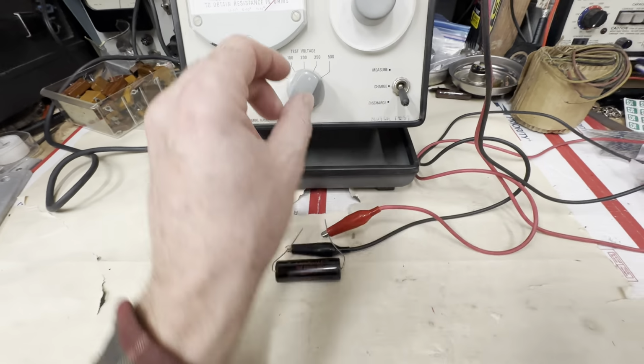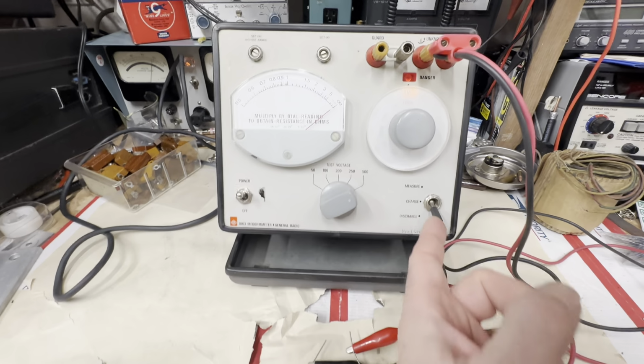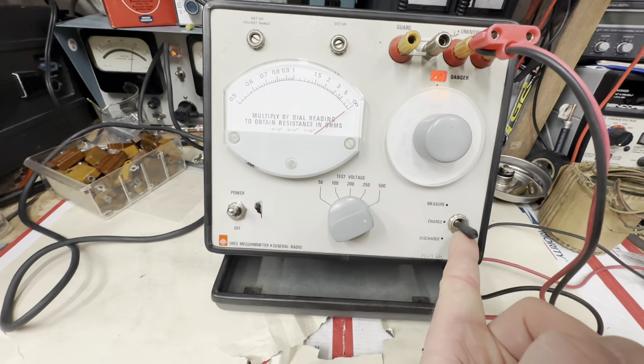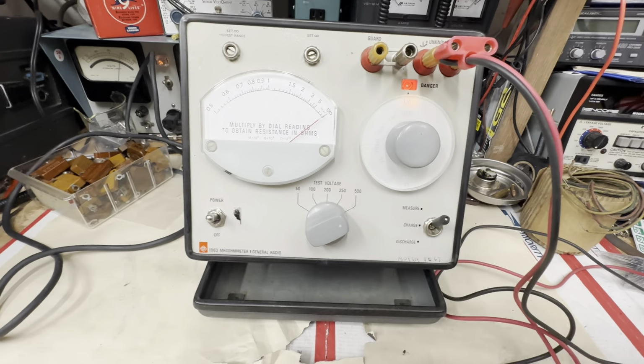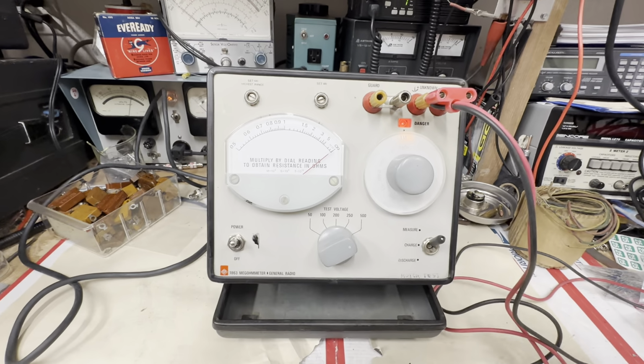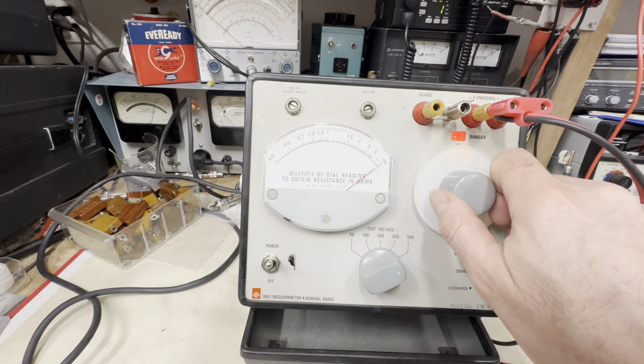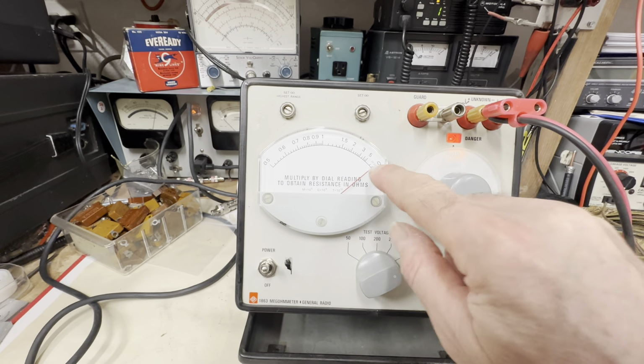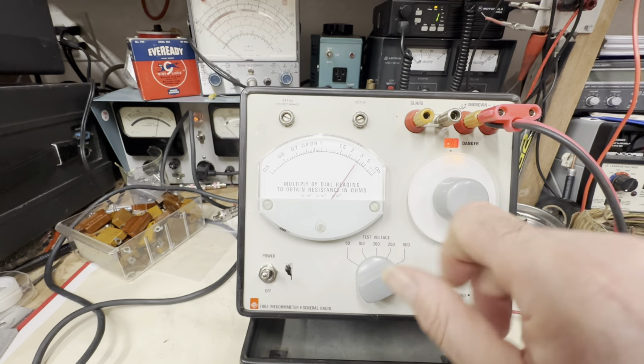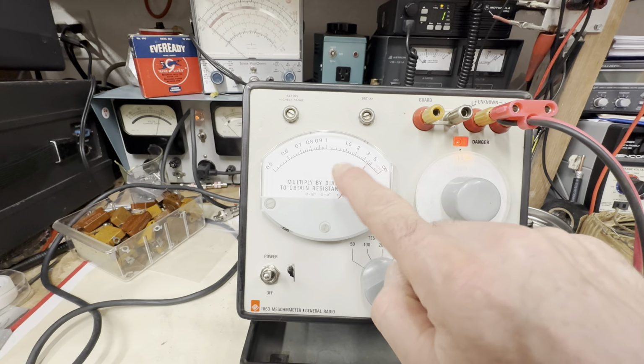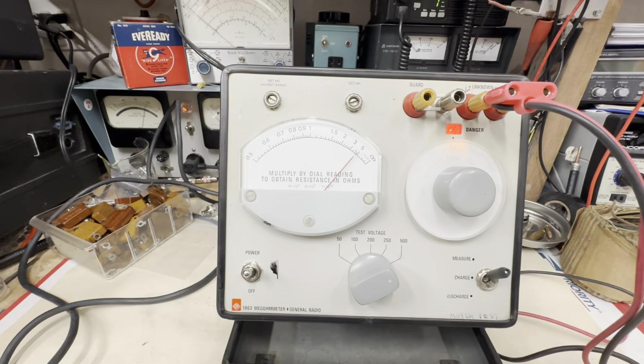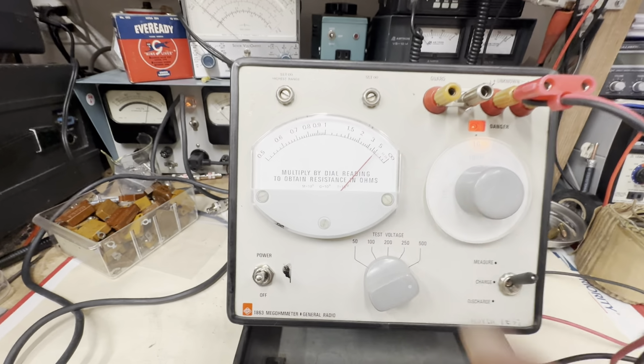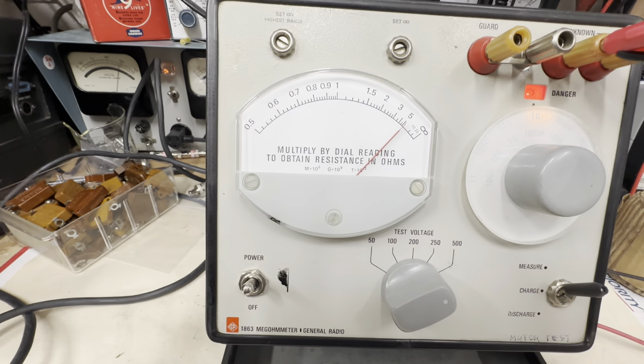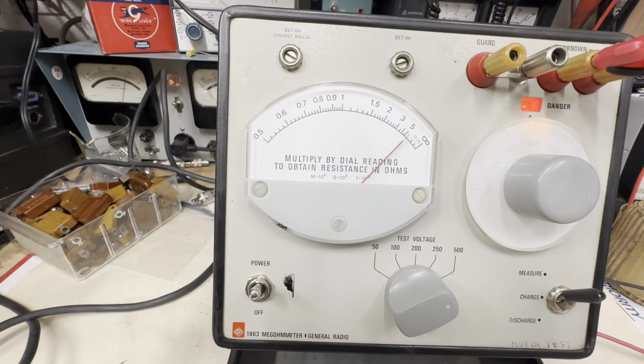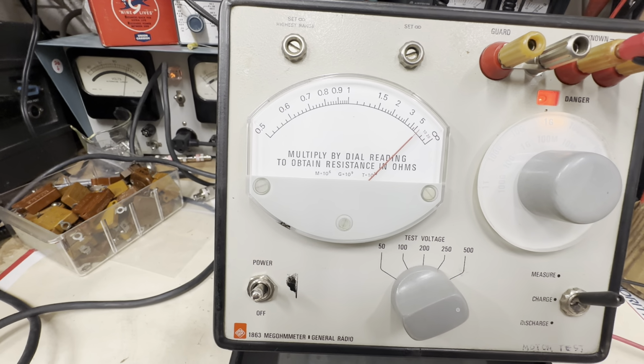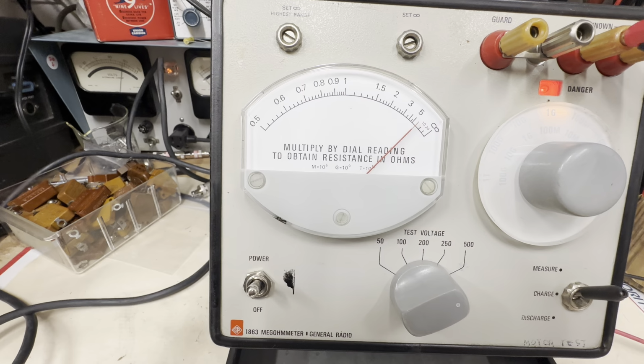Let's go ahead, and what we're going to do is put a full 500 volts on this. Now we're going to go up here. This is going to charge up. It's on 1 meg. Okay, that's there. Now we're going to run this up. Okay, we're starting to see some at 100 megohms times 20. That's a 1 gig scale. So right now that capacitor is about 4 gig ohms. And you can see right now the needle is slowly but surely going up. What's happening is you've got some dielectric absorption and some polarization going on, so it may take a while for this thing to reach its final value.